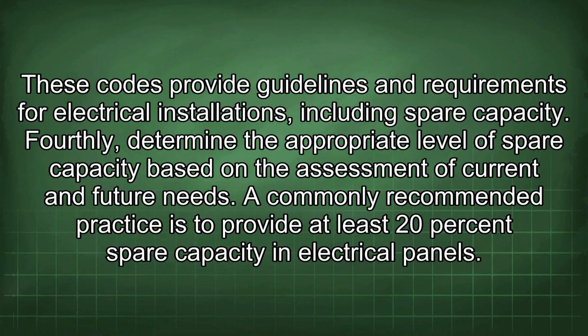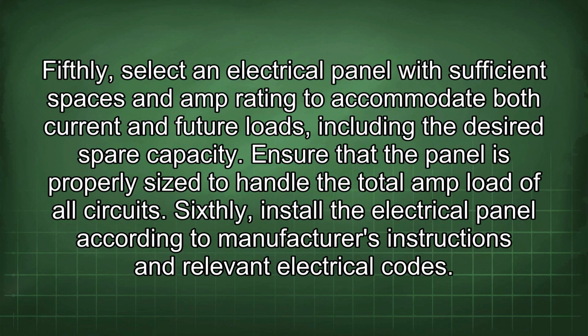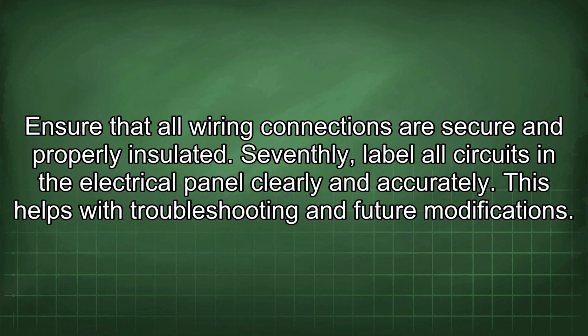Fourthly, determine the appropriate level of spare capacity based on the assessment of current and future needs. A commonly recommended practice is to provide at least 20% spare capacity in electrical panels. Fifthly, select an electrical panel with sufficient spaces and amp rating to accommodate both current and future loads, including the desired spare capacity. Ensure that the panel is properly sized to handle the total amp load of all circuits. Sixthly, install the electrical panel according to manufacturer's instructions and relevant electrical codes. Ensure that all wiring connections are secure and properly insulated.